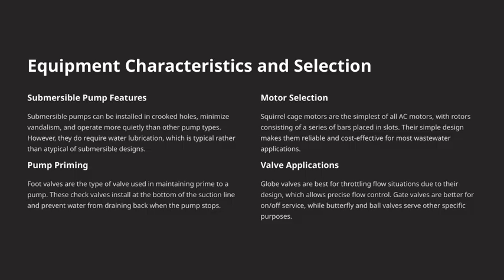Finally, on valve applications, different valves serve different functions. Globe valves are excellent when we need precise control over flow, such as throttling. They allow us to adjust flow rates accurately. Gate valves, on the other hand, are better suited for on-off operations. They open fully or close completely. Butterfly and ball valves serve other specific purposes, often chosen based on the particular application's needs, such as quick shutoff or flow regulation. Understanding these characteristics helps us make informed decisions when selecting equipment, ensuring reliability, efficiency, and longevity in our wastewater systems.